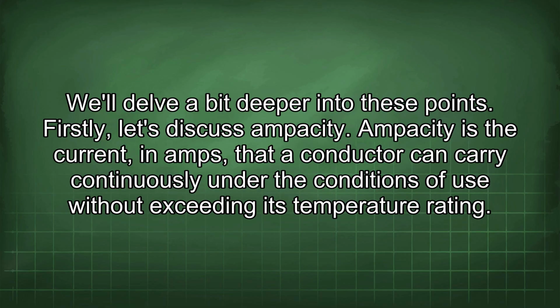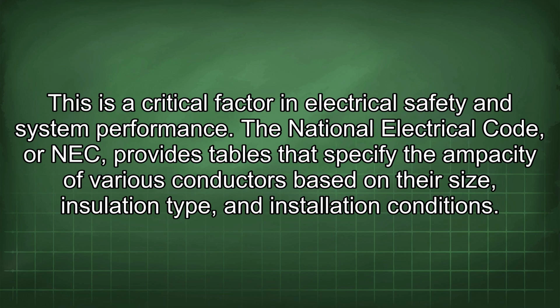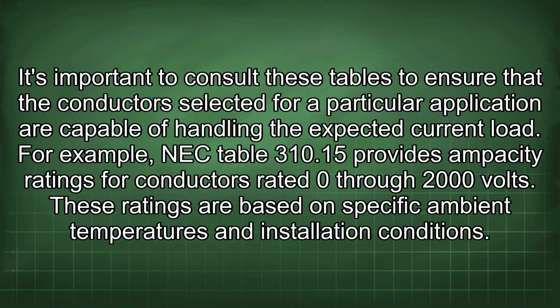Firstly, let's discuss ampacity. Ampacity is the current, in amps, that a conductor can carry continuously under the conditions of use without exceeding its temperature rating. This is a critical factor in electrical safety and system performance. The National Electrical Code, or NEC, provides tables that specify the ampacity of various conductors based on their size, insulation type, and installation conditions. It's important to consult these tables to ensure that the conductors selected for a particular application are capable of handling the expected current load.